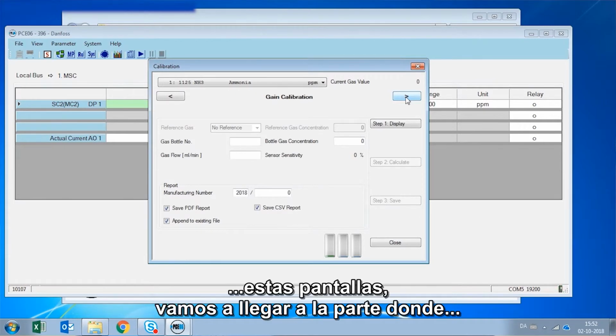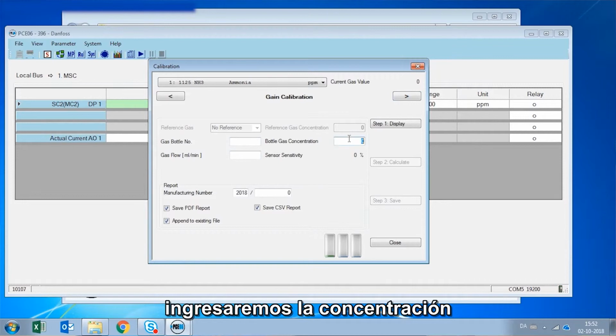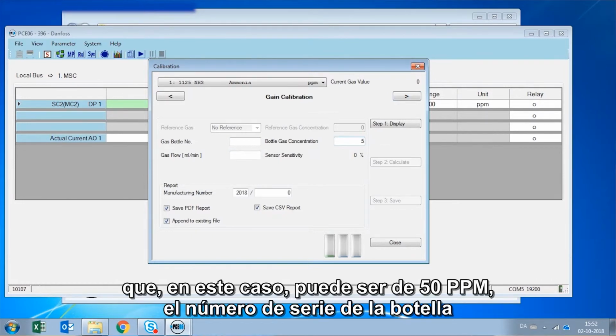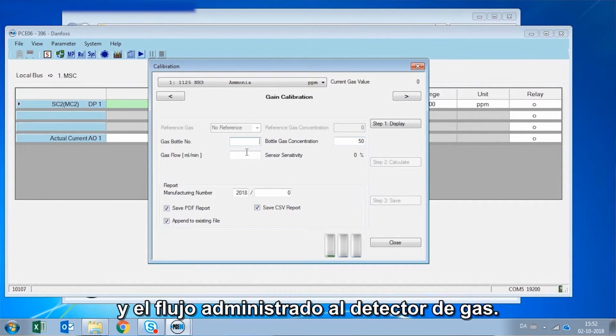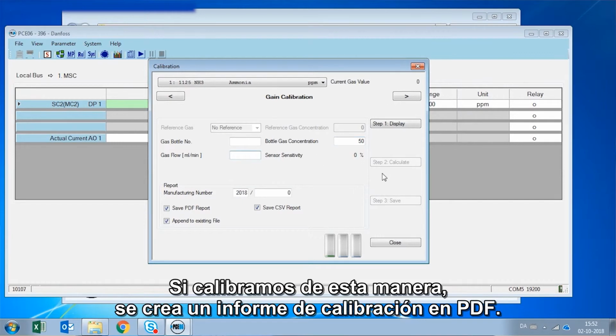And if we follow on these screens, we are going to get to the part where we are going to have to enter the concentration, which in this case can be 50 ppm. We can put the serial number of the bottle, the flow that we are administrating to the gas detector, and if we calibrate by this means, it's going to create a PDF report of the calibration.